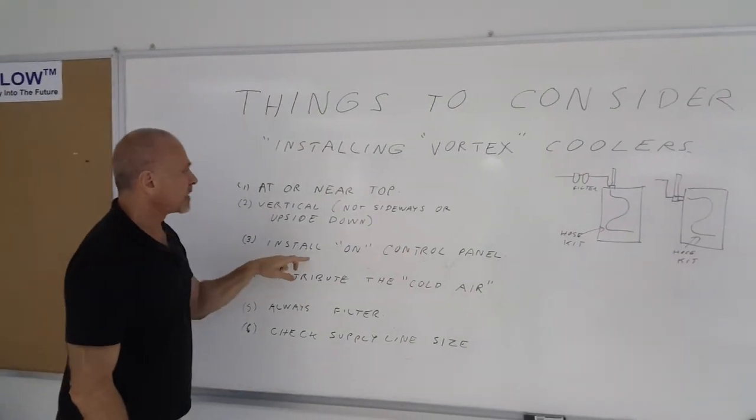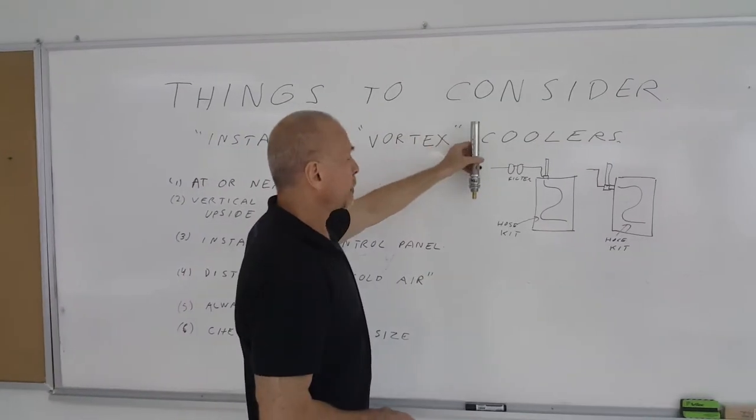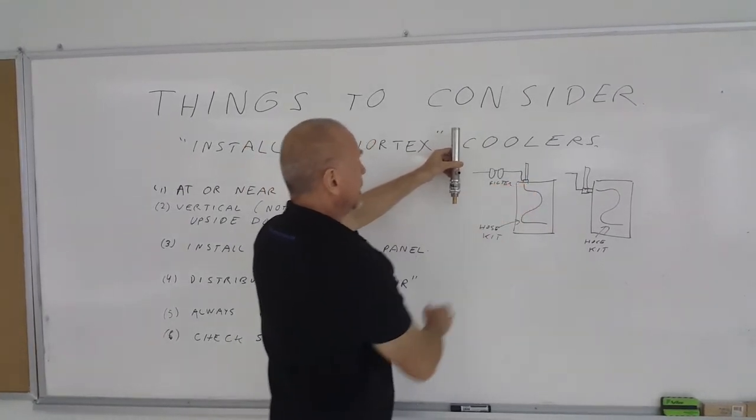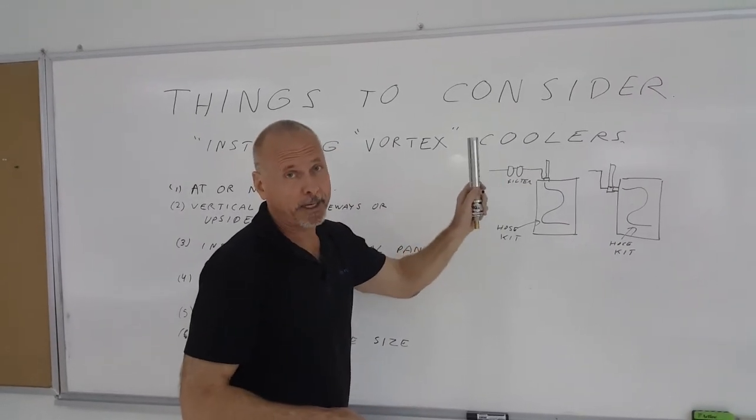Third, you want to install it on the control panel. We actually had a customer one time install the panel cooler outside the panel and had a hose leading into the panel. This causes a lot of cooling effect loss as it goes to the panel, thereby rendering it pretty much not very effective. So you'll want to actually mount it onto the panel.